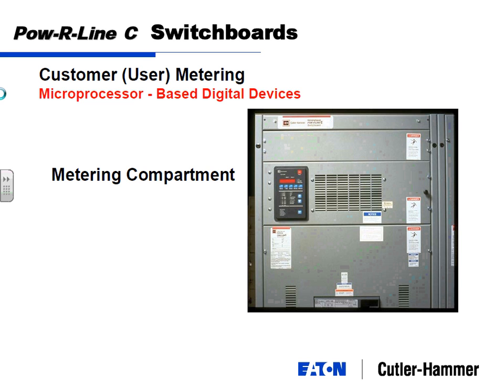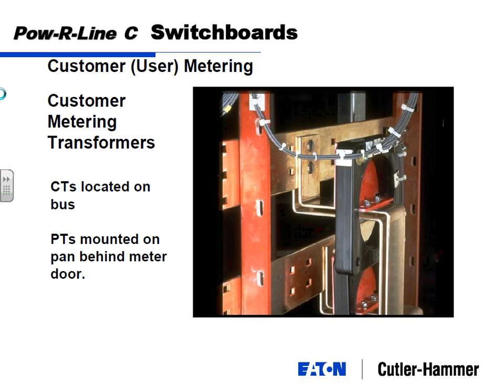The other things are like facility expansion. If you want to add load to your existing facility in a couple of years, you always have to understand where your facility is today. So the old adage is you can't manage your energy unless you can monitor it. For the customer metering, they put CTs. We factory install those right around the bus, maybe on the line side of the breaker or wherever actually makes sense, on the load side of the main breaker.